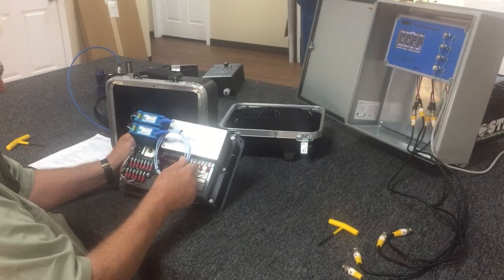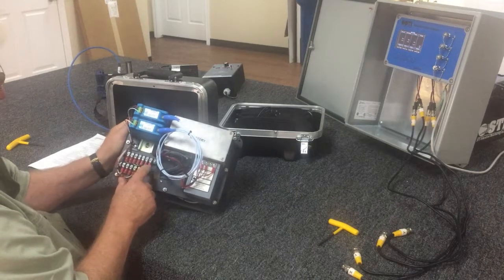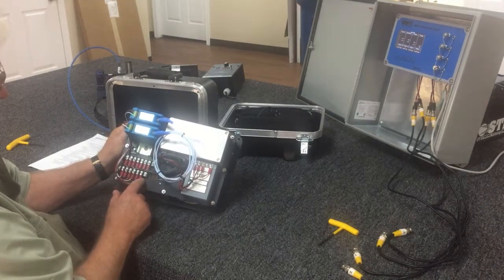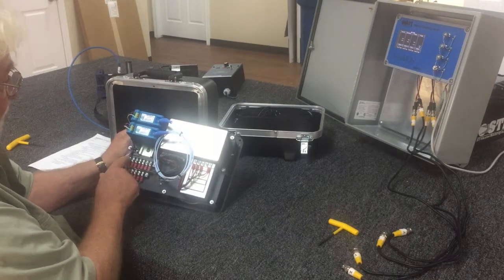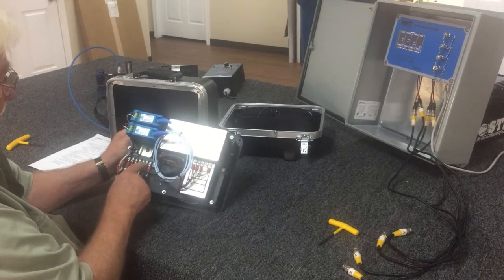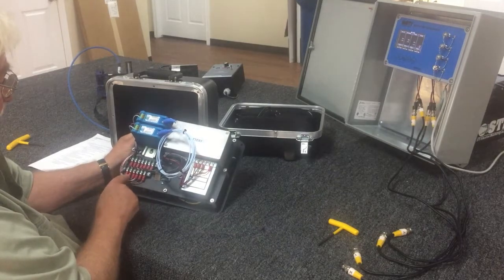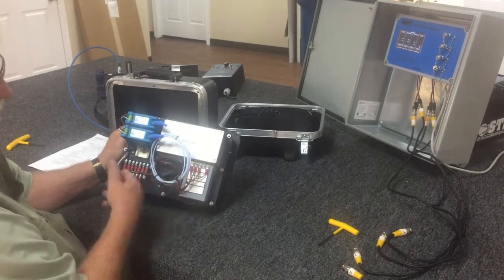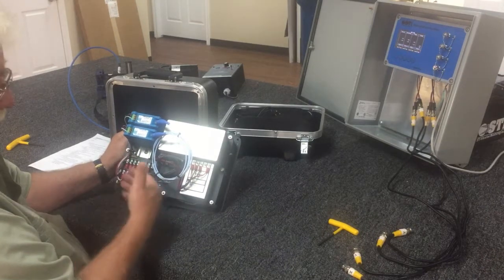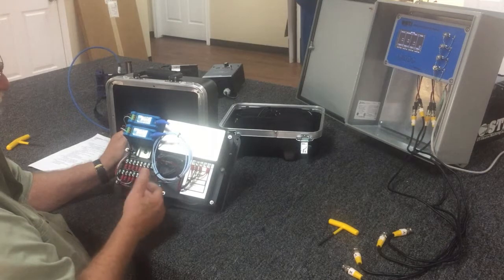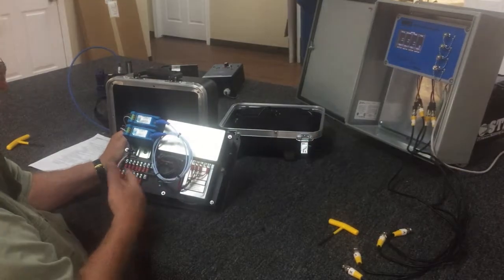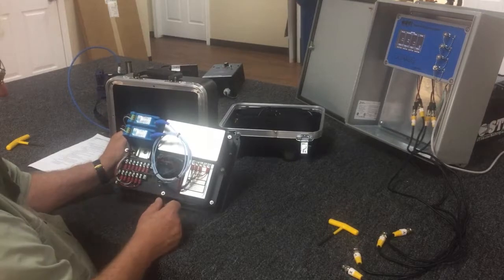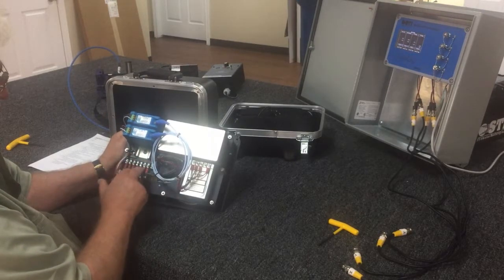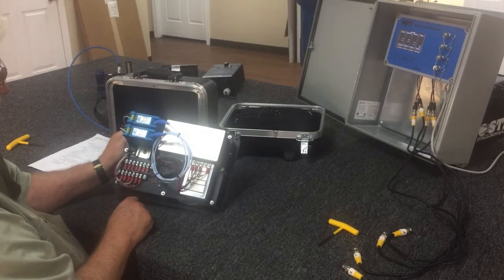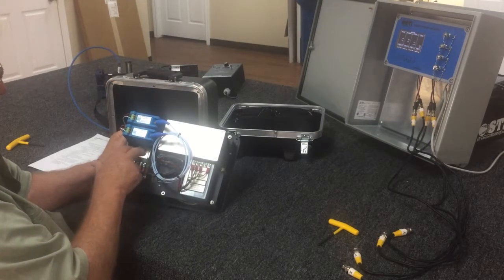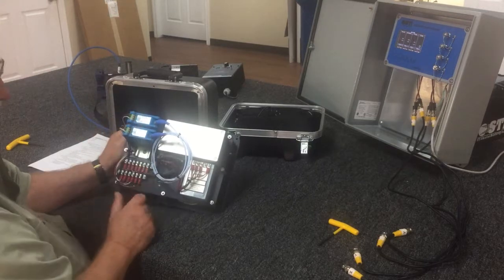The wires going out to the proximity probes. And here you can see the wiring for where your accelerometers and the proximity probes land. And they're all labeled. Top left one here is accelerometer vertical, accelerometer horizontal, phase. Down here it's proximity X, proximity Y. So everything is labeled, very easy for you to mount your sensors, because once again, sensors do not come standard. You can order them from us, we'll be happy to install them for you, or you can install them yourself as easy as what you can see here. You just simply put your sensors in and land the wires on the assigned points. Proximity probe, this has a DIN rail. If your proximeters don't have DIN rail, feel free to mount them flat against the surface itself.